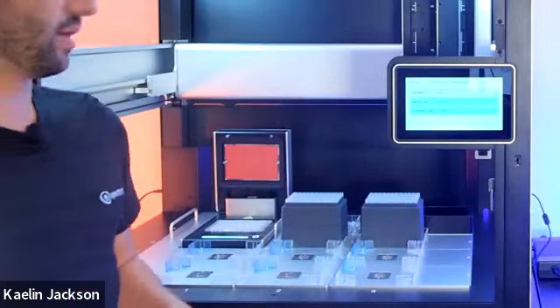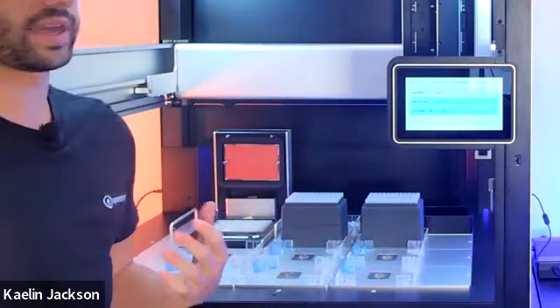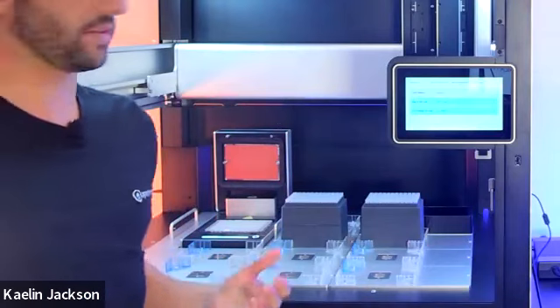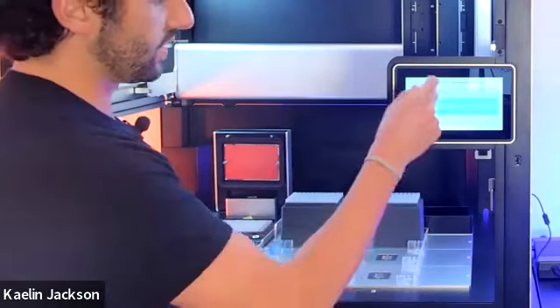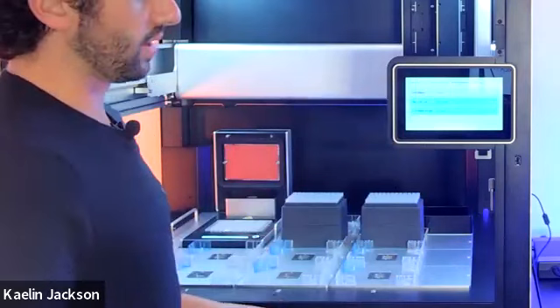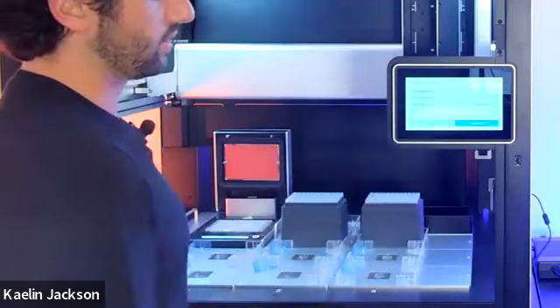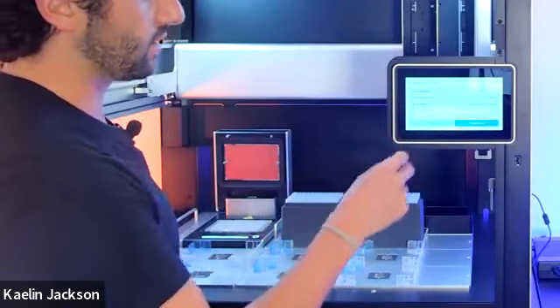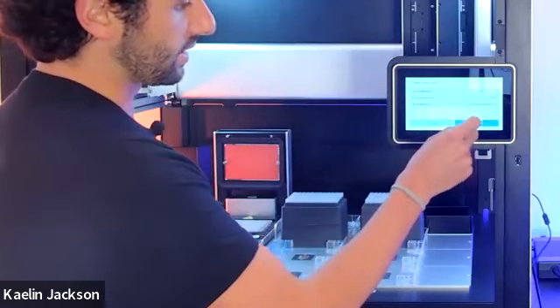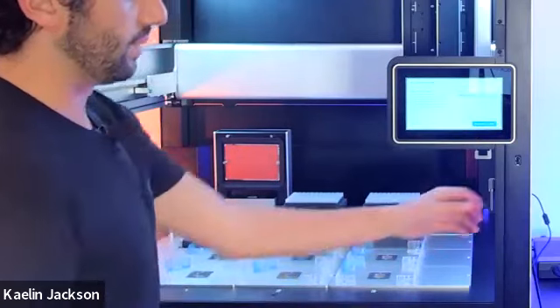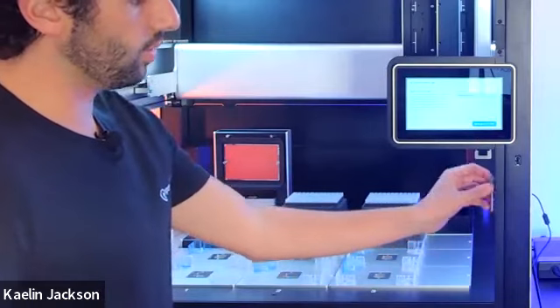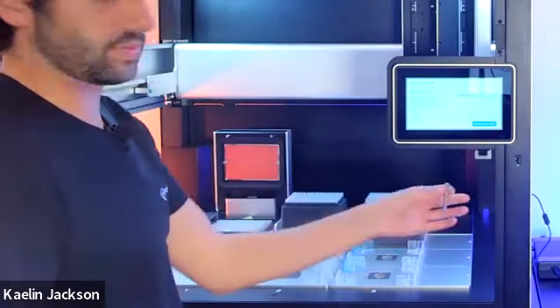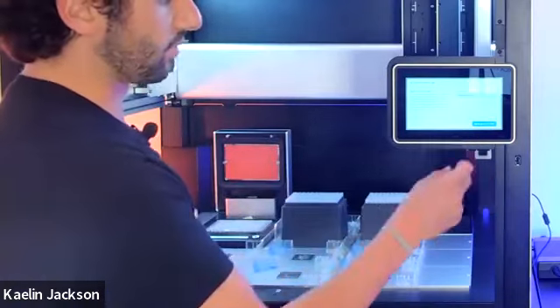Lastly, before I welcome John back in, I'd like to show you how simple it is to calibrate pipettes automatically on our platform. So in this case, we still have our P50 multi-channel pipette, 8-channel pipette on the right mount. I'll select that pipette on our display here. I'll select recalibrate, and I'll be prompted that I need my calibration probe, which is conveniently accessible via magnet on the frame of the robot.